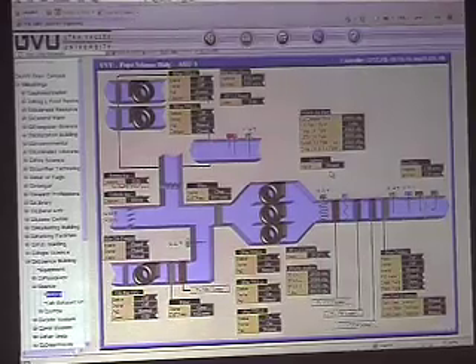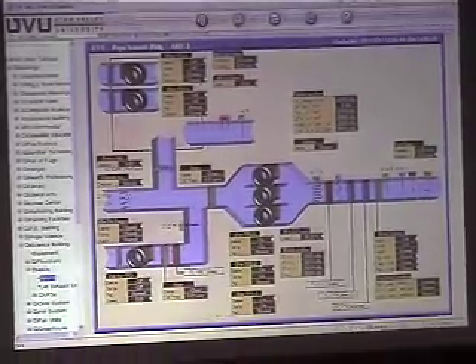If any of your safeties trip out, so you've got your high duct static, your freeze stats, or your fire alarms, it'll show us a safety alarm here on the screen, and that will shut down the supply fans as well as the outside air fan. All the outside air dampers will shut, and the return air damper will open.